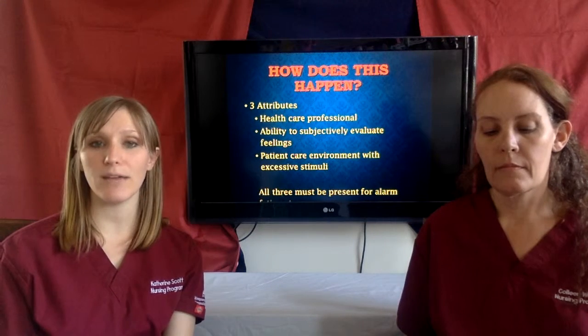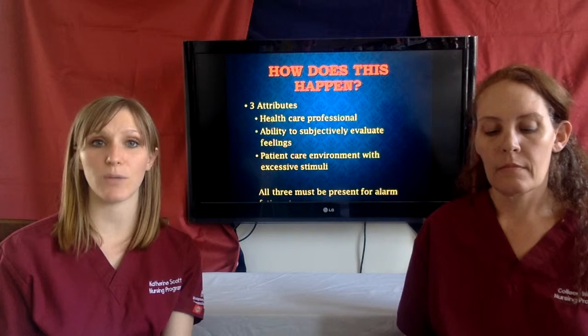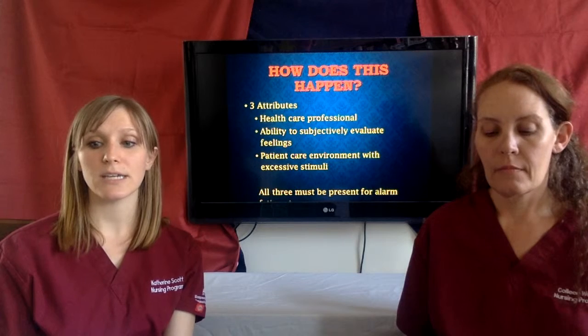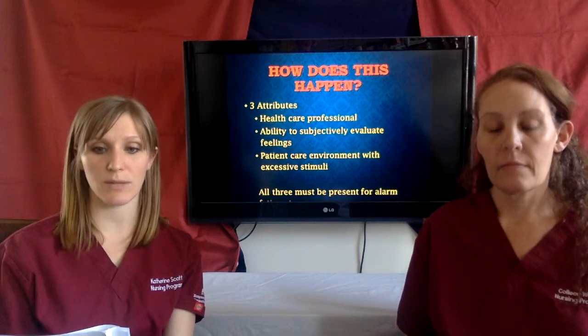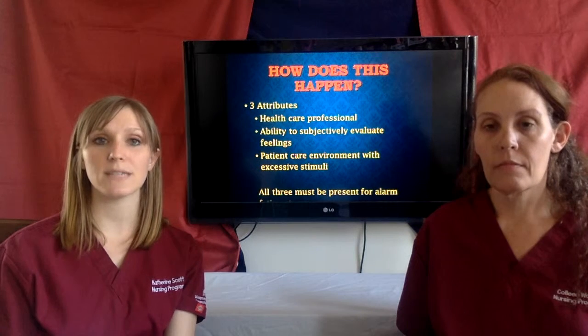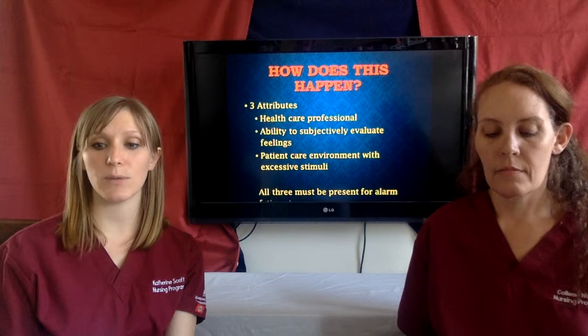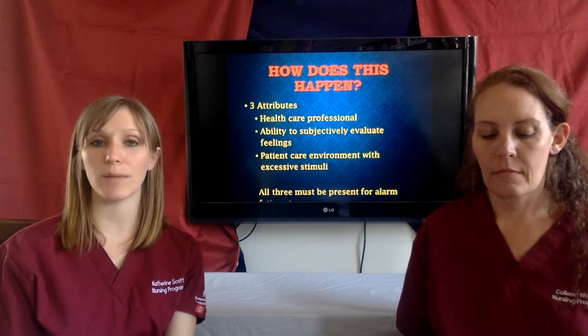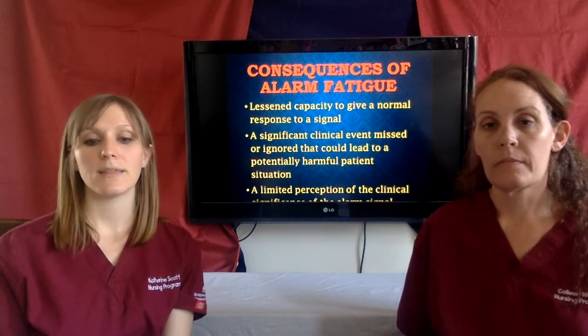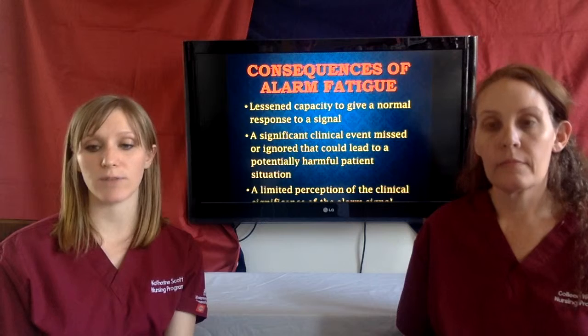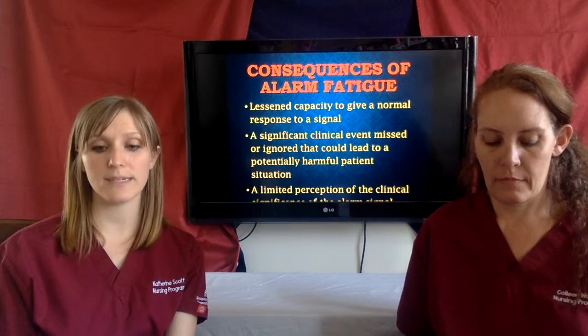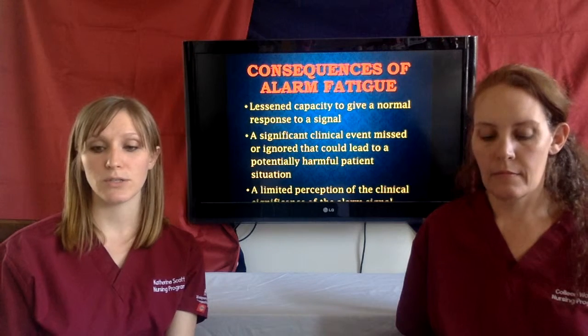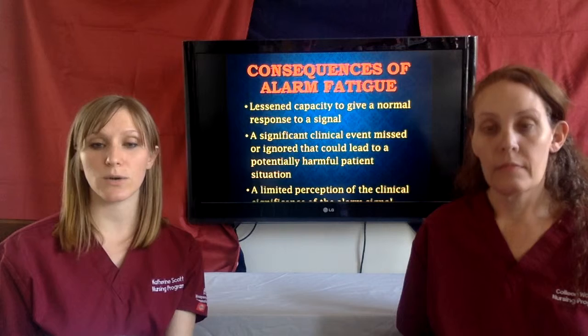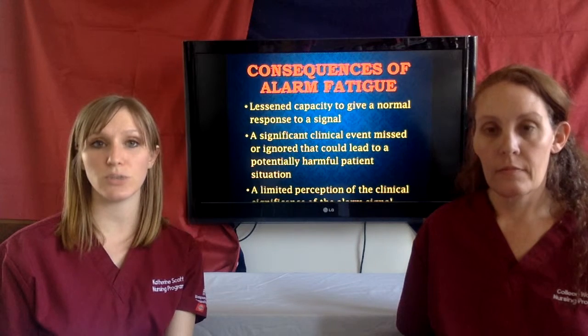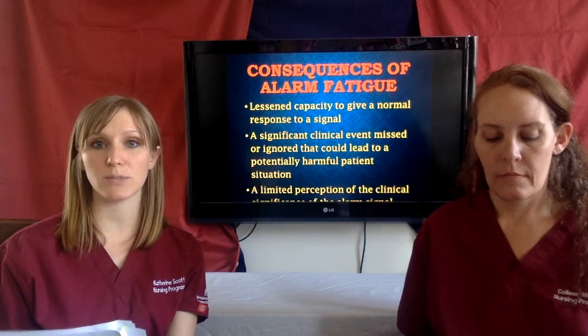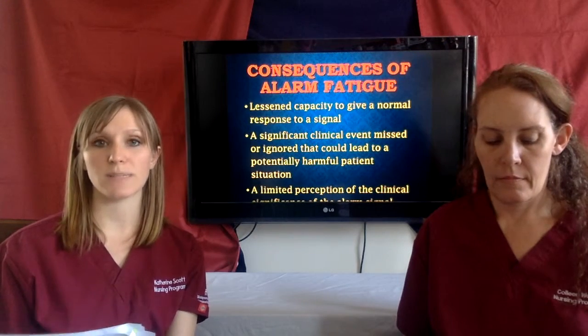As a new nurse, we already have 2 out of the 3 things that put someone at risk for developing alarm fatigue. The only thing missing is working in a patient care environment with excessive stimuli. Almost all of us will find a job in this type of environment after graduation, so we will have completed all of the dangerous puzzle pieces forming alarm fatigue. These attributes contribute to the consequences of alarm fatigue, which are 1. A lessened capacity to give a normal response to a signal. 2. A significant clinical event missed or ignored that could lead to a potentially harmful patient situation. And 3. A limited perception of the clinical significance of the alarm signal.